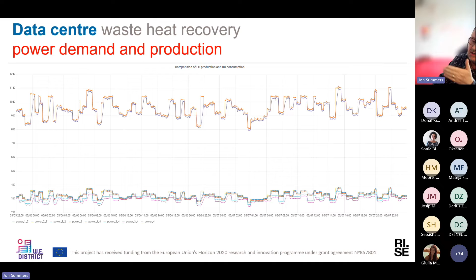And so some of the results that we got in terms of the monitored energy consumption, from the 11th of January 23 to the 16th of June 23: we consumed 72 megawatt hours of biogas, and the solid oxide fuel cells were able to produce 39.4 megawatt hours of electrical generation in that period. And so they are 54.6%. The whole system, the stack of 9 fuel cells, was 54.6% efficient in terms of generating electricity. The rest of the energy is heat and some other parasitic loads.